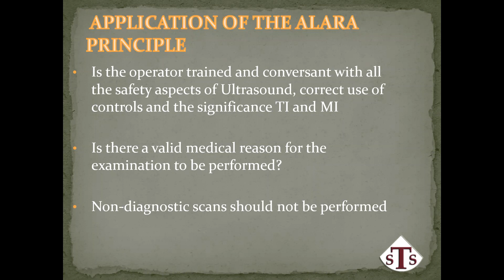Now, there's another side to this apart from safety. If you work at high intensities, what you are actually doing is effectively widening the beam. And from physics, we know that the lateral resolution is best when the beam is narrow. So if you scan at 100%, not only is it impacting on safety, but it is impacting on your image resolution as well. So there's two reasons for dropping your output power from 100% down.